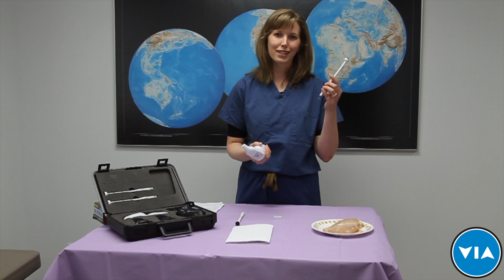for your next patient. Let's go through some troubleshooting. So if for some reason the device is not working properly, you can determine whether it's in the probe itself or in the handle. So when you attach the handle and the probe, if for some reason when you turn it on, all of the lights come on and they blink, that means there's a problem with the probe. If you turn it on and nothing happens, no lights, no anything, that means that there's a problem with the handle. And there's no repair necessary.